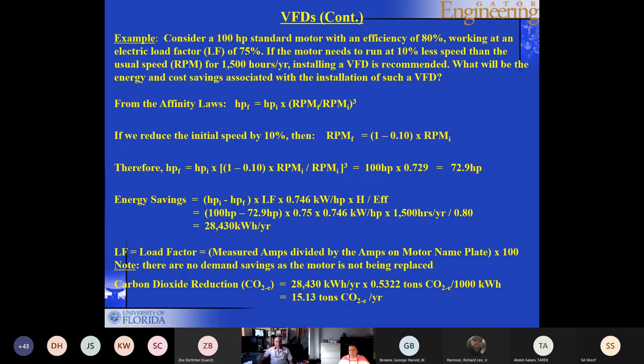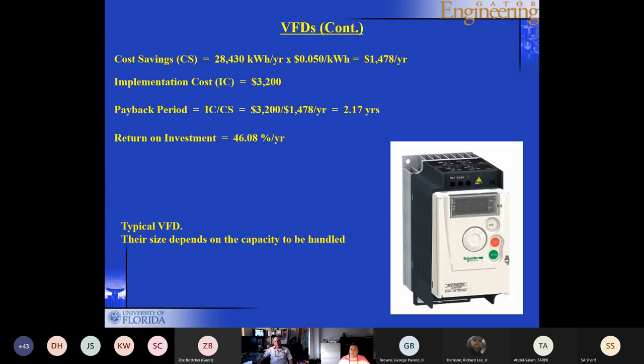All right, so that's again another possibility, which is the variable frequency drive. This is how it looks. It costs about $3,200 installed. That's including the installation cost. In this case, the cost savings will be the amount of energy that you save, the 28,430 kilowatt hour per year. You multiply it by the cost of energy, $0.05 per kilowatt hour. You end up with $1,478 per year.